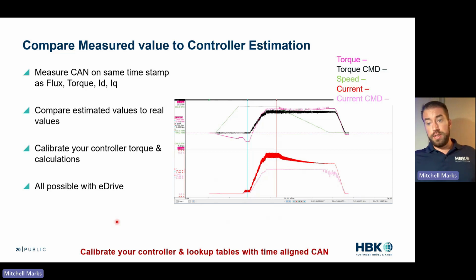Now, the other thing we're seeing is the controller is calculating torque on its own. You know, it's calculating flux, it's getting to torque eventually. So we can compare measured values to the controller estimation by measuring the CAN bus of the system. And now you're getting your voltages, your currents, your torques, your fluxes, and your calculated torque, your calculated ID, your calculated IQ from the inverter. Play that in all one place. So we can measure the CAN on the same timestamp, compare that to your values. You can look at what that difference is and start to calibrate your torque estimation.